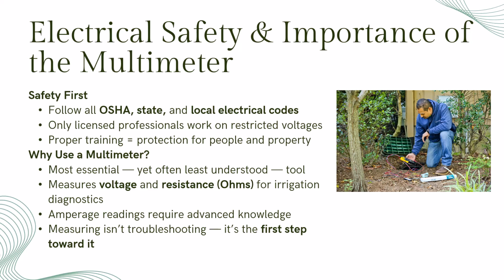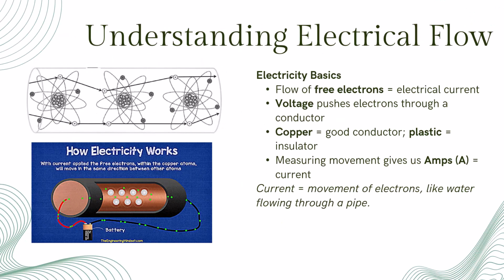For irrigation, we primarily use a multimeter to measure resistance, ohms, and voltage. Measuring current or amperage can be useful for experienced technicians, but isn't typically part of routine troubleshooting. Remember, measuring and troubleshooting aren't the same thing. Measuring gives you the data that reveals trends, component degradation, and the clues needed to fix problems before they can cause system failure. To use a multimeter effectively, we first need to understand what electricity really is.